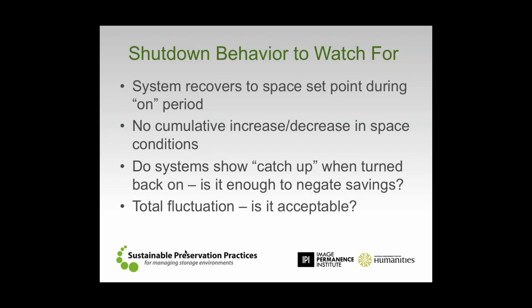Now the one exception is if you're using a refrigerant-based or a DX system, direct expansion. Those units are of a nature that they typically will cycle in operation. And what you find then is if it starts to cycle more often or for longer periods of time, then you can start to use more energy than what was used without the shutdown. But even in those circumstances, when we started running the numbers and looking at the actual energy consumption, what we found is that when the system started up the next day, the unit might use roughly between 15 and 20% more energy for a limited amount of time in order to catch up to that set point condition, which means that from the overnight perspective, if you're only losing 15 to 20% of the total energy that you saved overnight and still coming out 80 to 85% ahead, that's worthwhile.